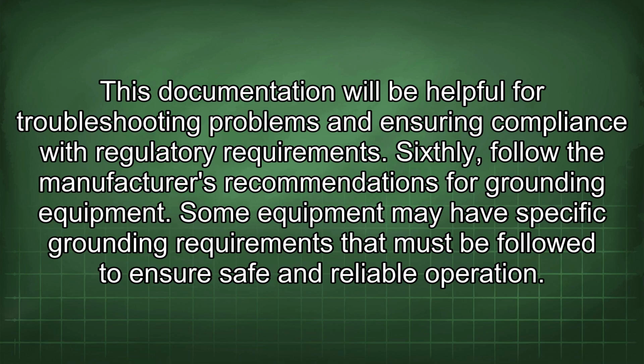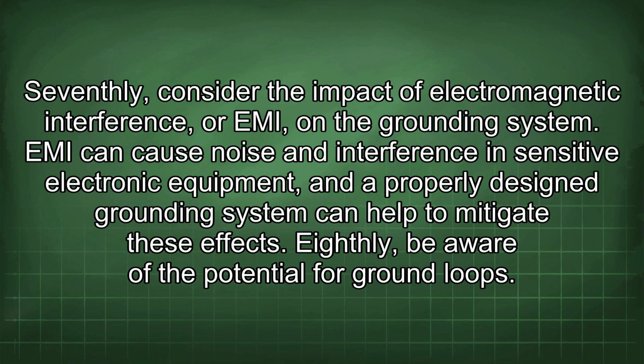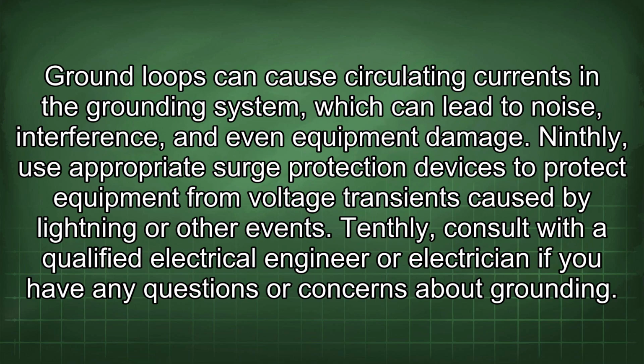Sixthly, follow the manufacturer's recommendations for grounding equipment. Some equipment may have specific grounding requirements that must be followed to ensure safe and reliable operation. Seventhly, consider the impact of electromagnetic interference, or EMI, on the grounding system. EMI can cause noise and interference in sensitive electronic equipment, and a properly designed grounding system can help to mitigate these effects. Eighthly, be aware of the potential for ground loops. Ground loops can cause circulating currents in the grounding system, which can lead to noise, interference, and even equipment damage. Ninthly, use appropriate surge protection devices to protect equipment from voltage transients caused by lightning or other events. Tenthly, consult with a qualified electrical engineer or electrician if you have any questions or concerns about grounding.